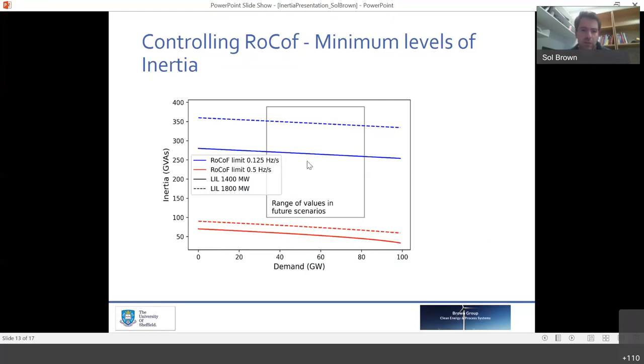So here we have our current at the top. We have the blue curves, which are the current state of the RoCoF limits set by the grid code, and the bottom are the limits that are set for the future. And here we have the current largest infeed loss and the projected forward largest infeed loss, where we have Hinkley Point C, and we can see the curve of the amount of demand on the network and the amount of inertia provided.